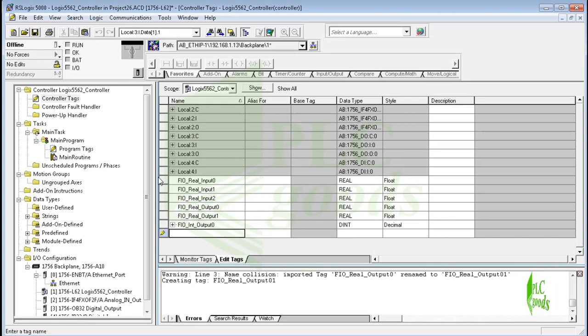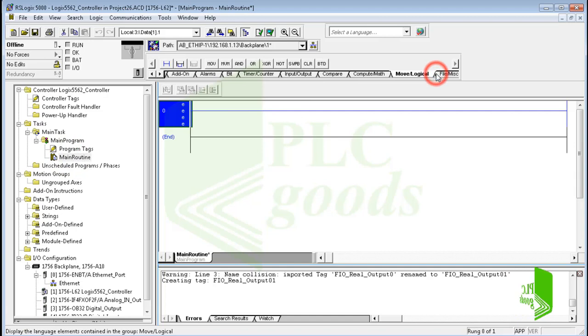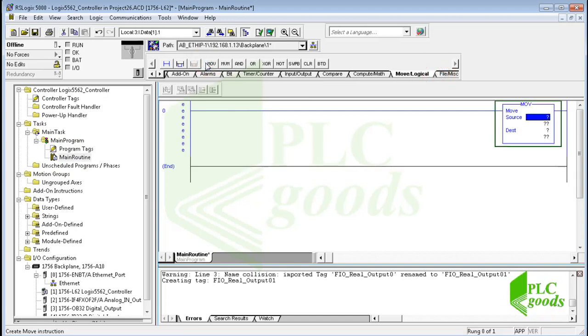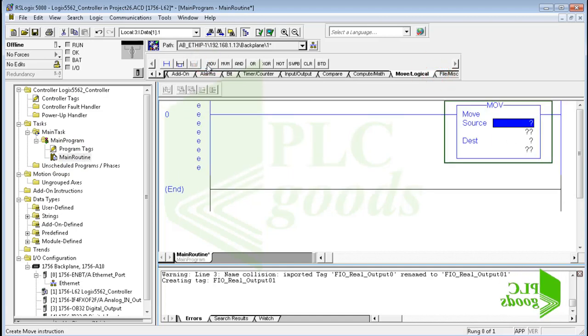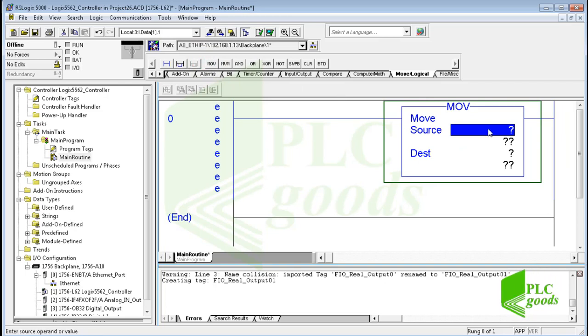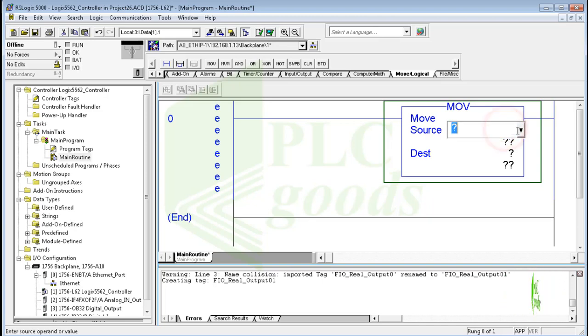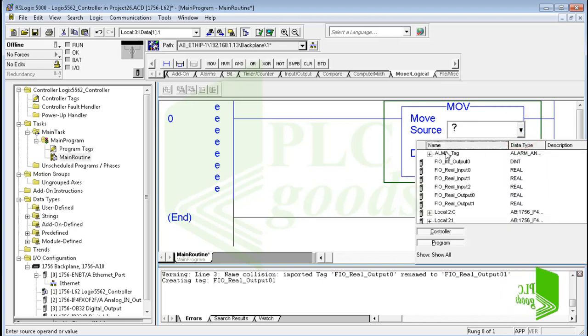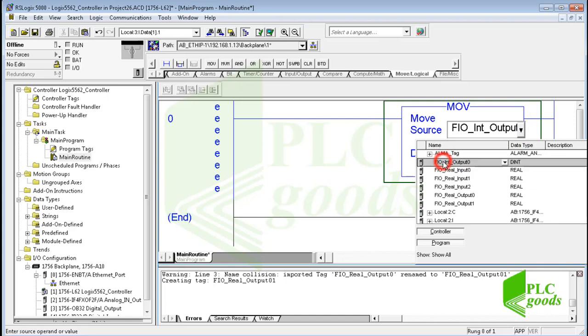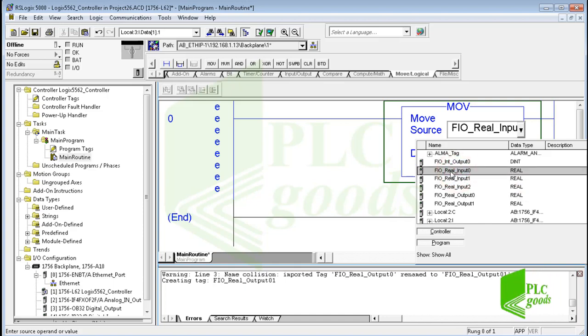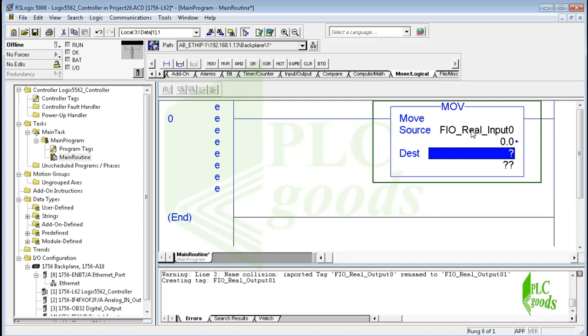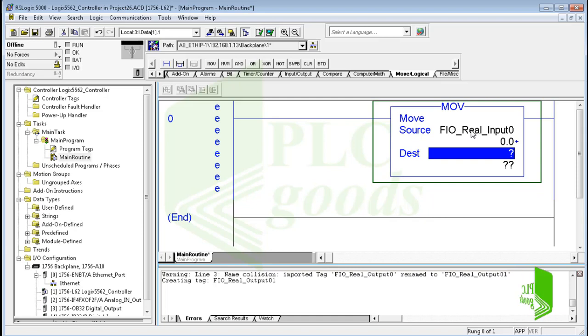Let's write the PLC program. If you remember, each potentiometer sends a voltage between 0 and 10 to my PLC. Also, each valve can be controlled by a voltage between 0 and 10. So I can use a move instruction to get voltage from each potentiometer and send it directly to the related valve. Pay attention, here I want to tell you another way of using tags or addresses. Here I want to refer to the first potentiometer voltage. I will connect it to the first virtual analog input with this address, FIO_Real_Input0. So the controller will use its value which is a number between 0 and 10. But this address is a little hard for a new person to understand the PLC program logic.